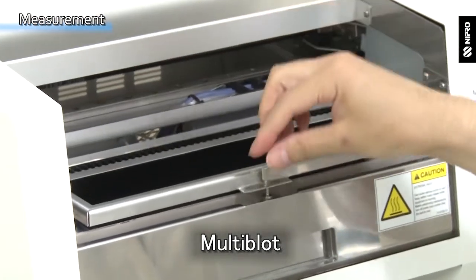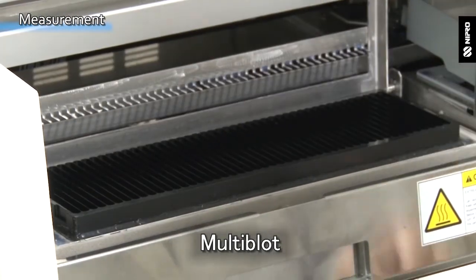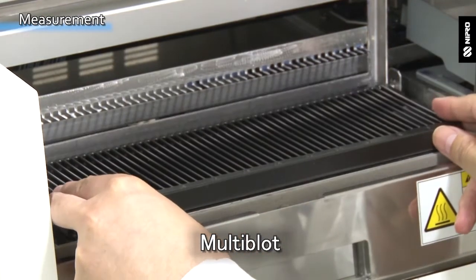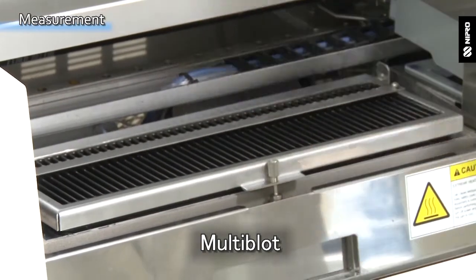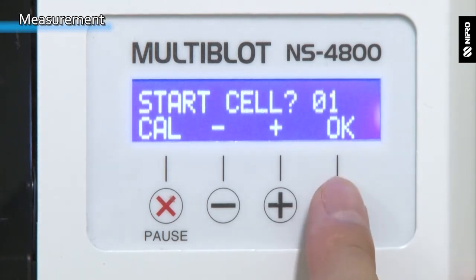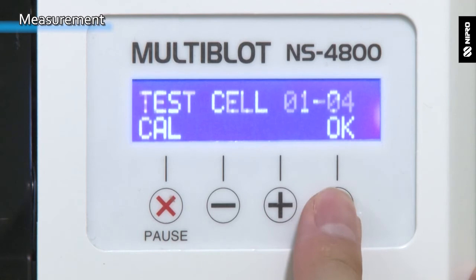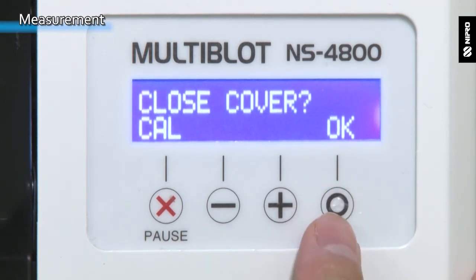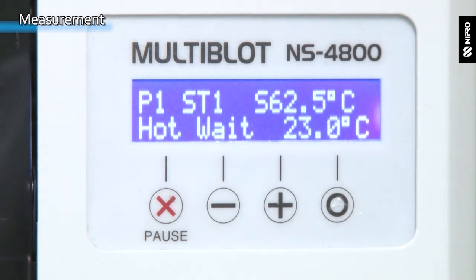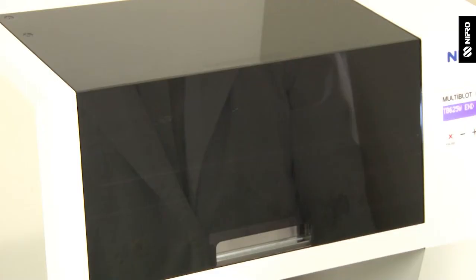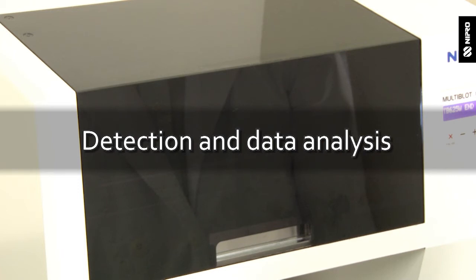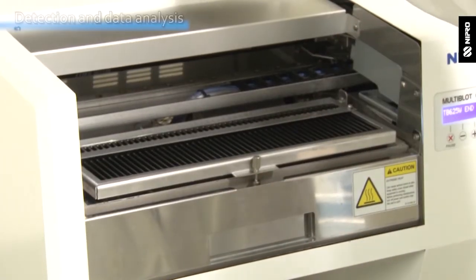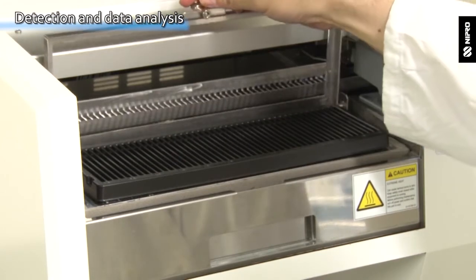Open the front cover and unfasten the tray holder of the multi-blot. Place the tray on the heat block of the machine and fix the tray with a holder. Close the front cover. Select the program through the operation panel. Following the indication on the display, run the program. After the program is completed, open the front cover to take the tray out of the machine.